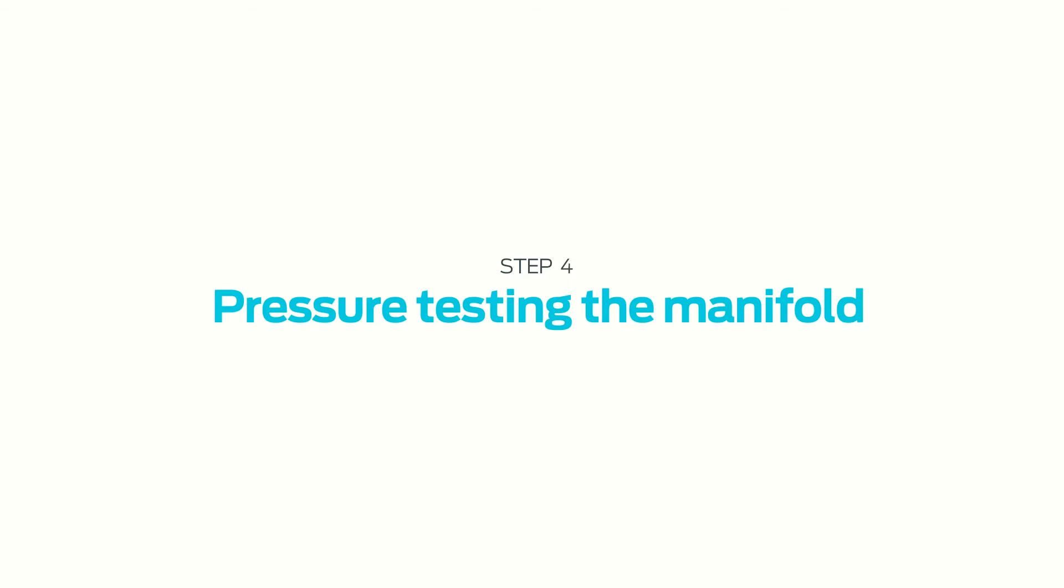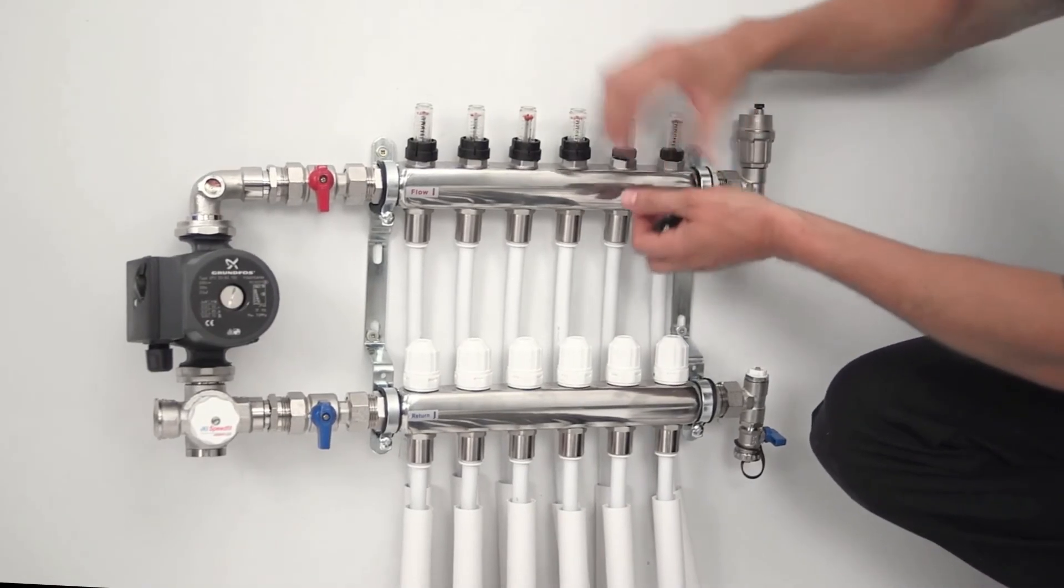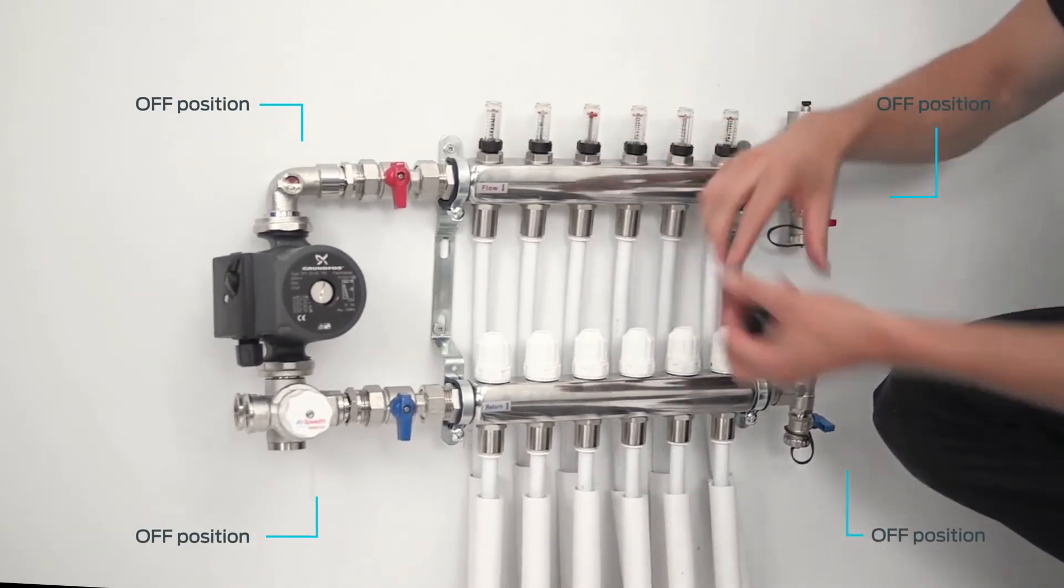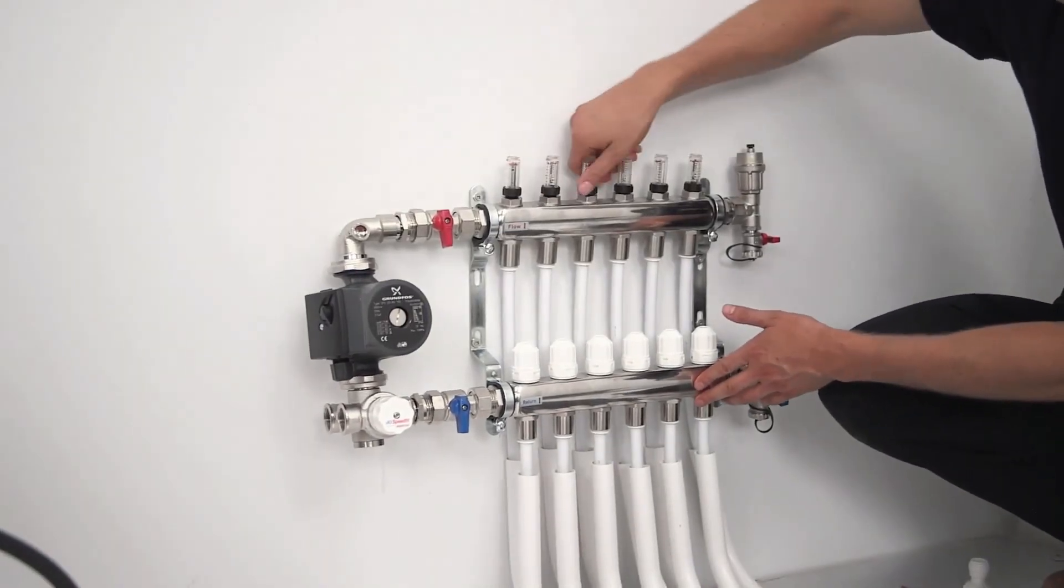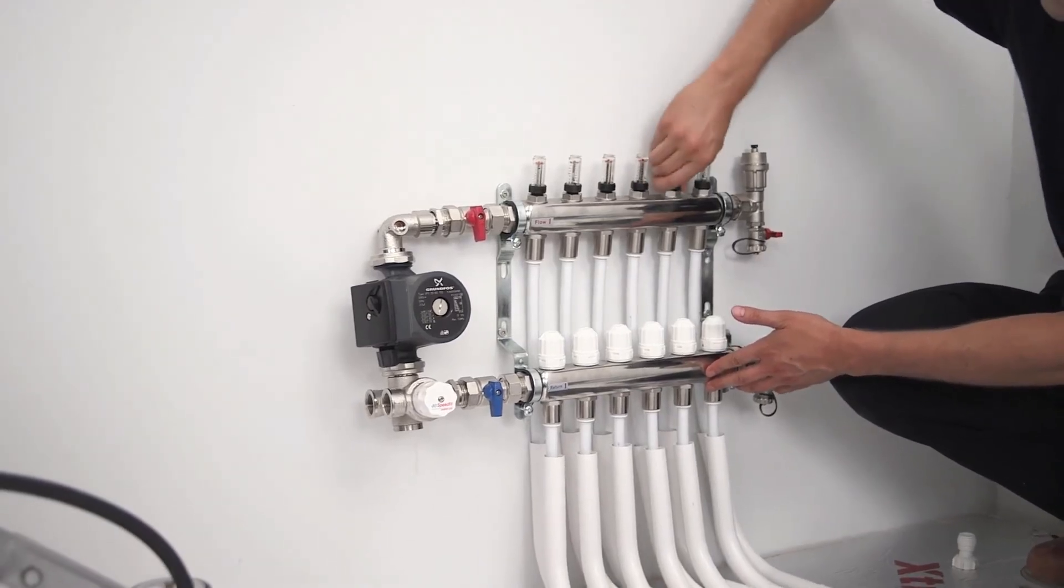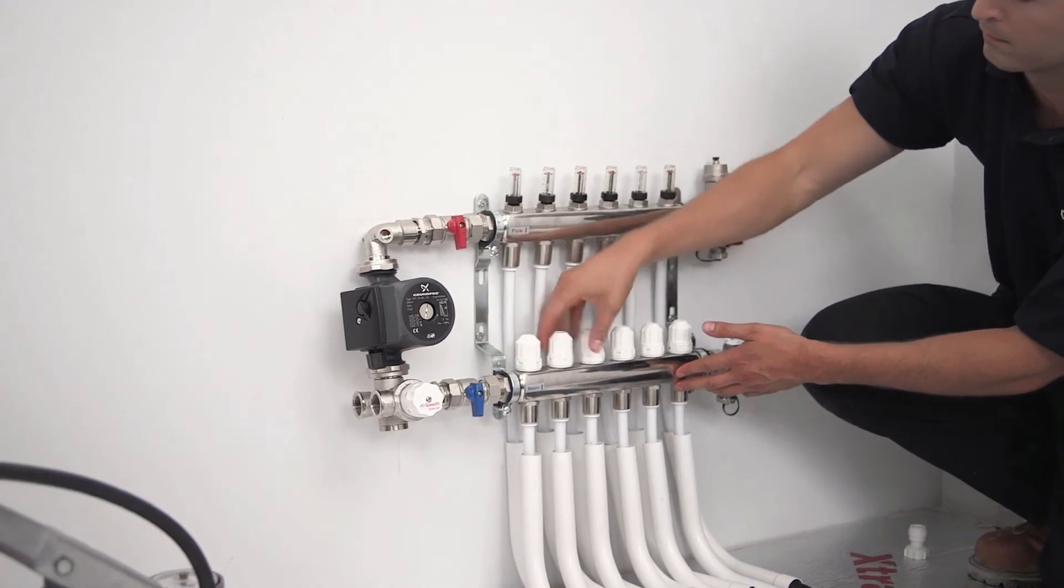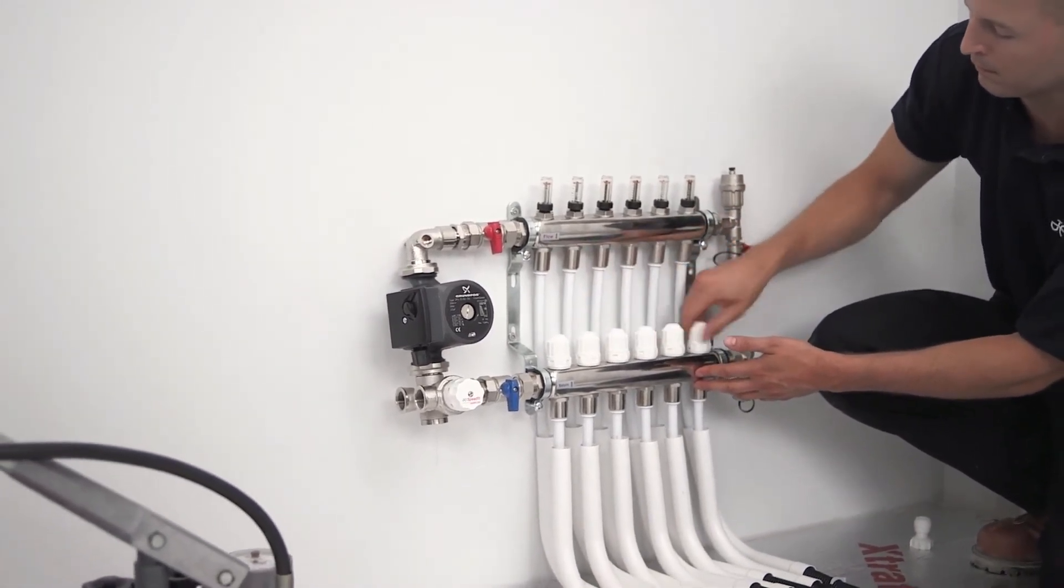Pressure testing the manifold. Isolate the manifold from the heating system by turning the ball valves to the off position. Open all flow gauges at the top of the manifold by lifting the locking cover and turning the adjuster anti-clockwise. Ensure all temporary adjuster heads are in the fully open position by turning anti-clockwise.